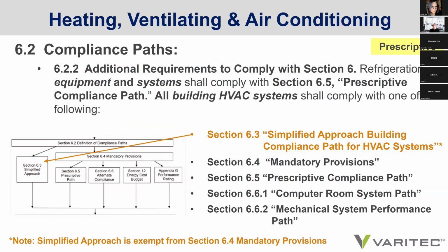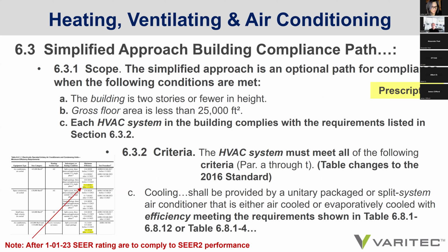So looking at the compliance path, the prescriptive simplified approach building compliance path for HVAC systems. What is it? It is a pathway that can be used if the building is 2 stories or fewer in height, a gross floor area is less than 25,000 square feet, and each HVAC system in the building complies with the requirements listed in section 6.3.2. And that criteria is that the HVAC system must meet all of the following criteria, including there are significant changes to the tables shown from the 2016 standard to the 2022 standard.